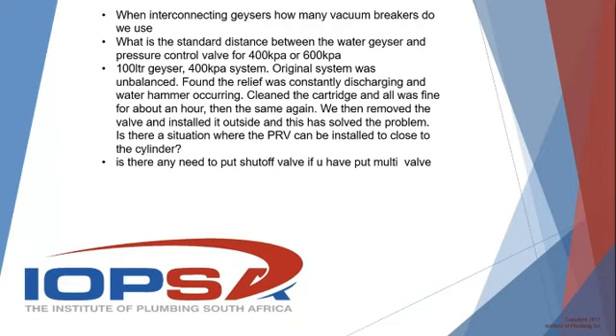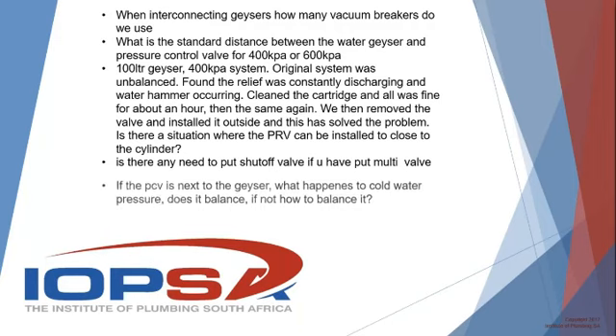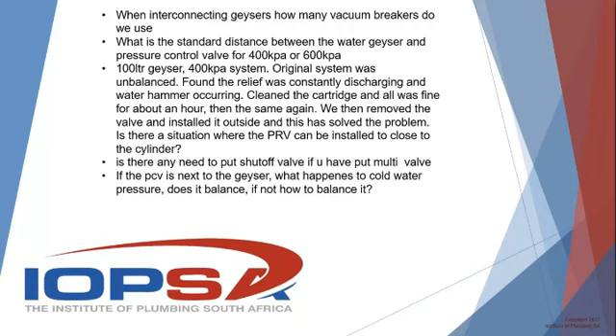Yeah, definitely. SANS 10252 very clearly shows that there must be a specific isolating valve, as I said, where you have water entering a building with separate occupation. And then it carries on to say that if there is an integral shut-off, that is not to replace a specific isolating valve. So you must still have the specific isolating valve. And the reasoning behind that is, if you need to replace that valve, where do you shut off the water? You need to have that specific isolating valve where you can isolate everything to remove the pressure control valve.